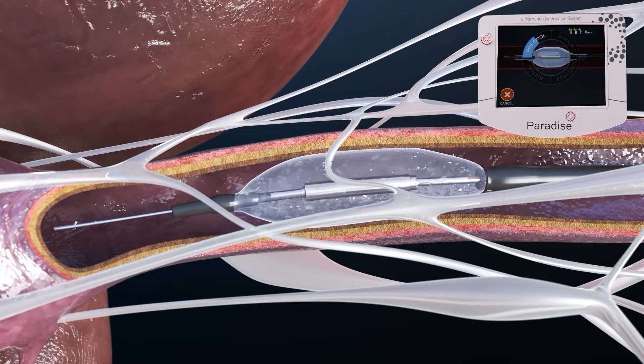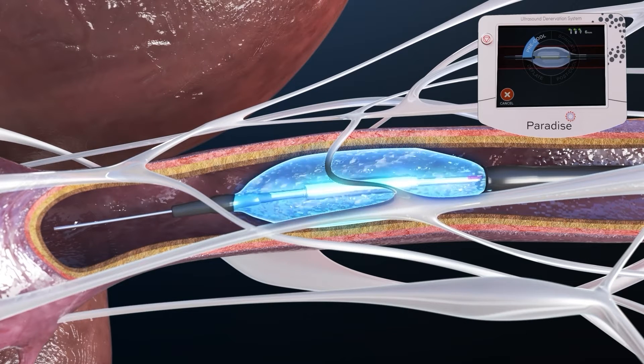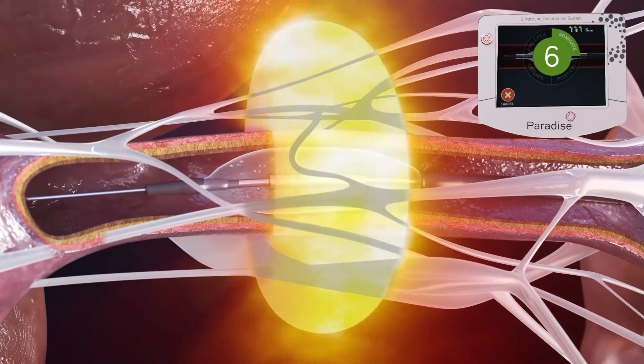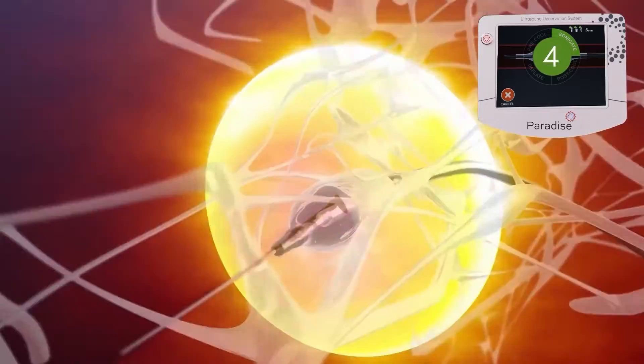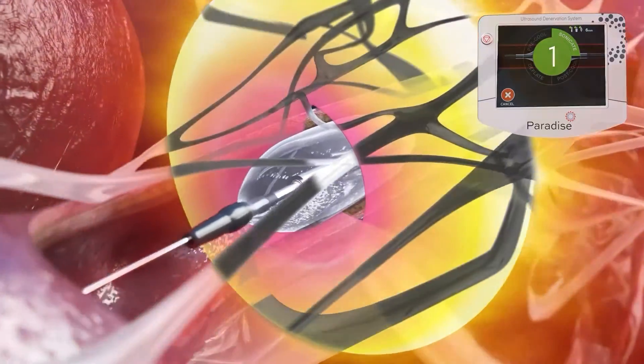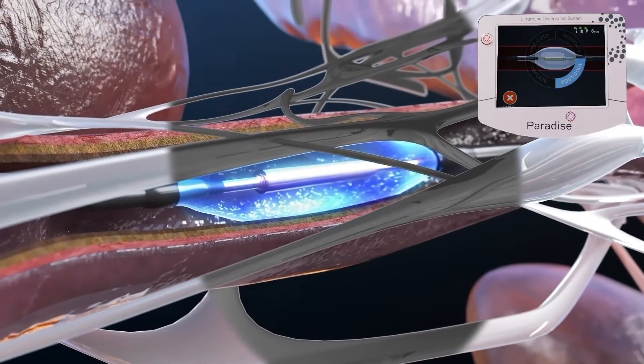The sonication process begins with the hydro cooling system, which circulates sterile water through the balloon to protect the arterial wall. Each sonication lasts just seven seconds, enabling an efficient procedure while reaching the majority of the nerves surrounding the main renal artery.